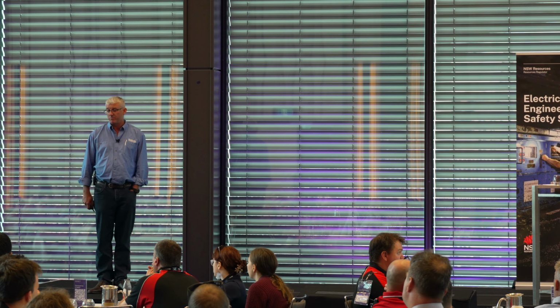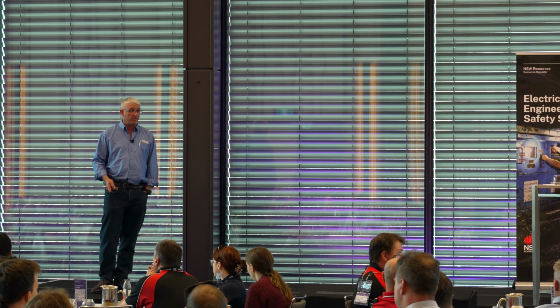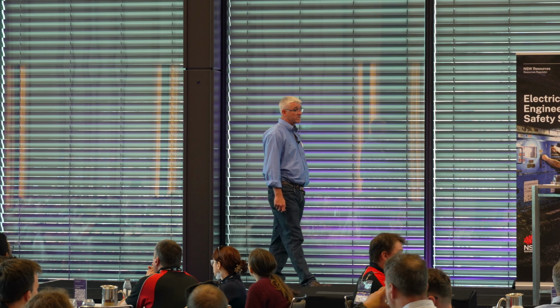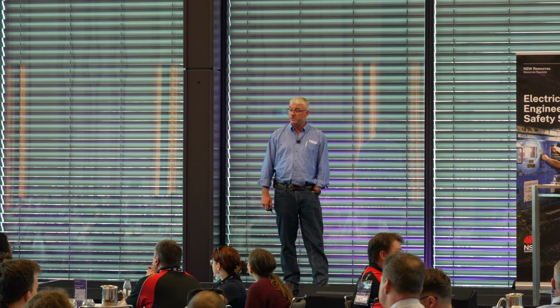People had put the wrong thermal magnetic protection bolted onto the bottom of the circuit breaker, and whether they'd done that because the breaker had failed and that was all we had on site as a spare part, I'm not sure. But that was some of the stuff we found. It was a really healthy process to be able to do that audit and go, didn't even know that existed, didn't know it was out there.